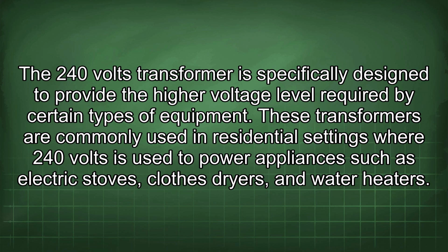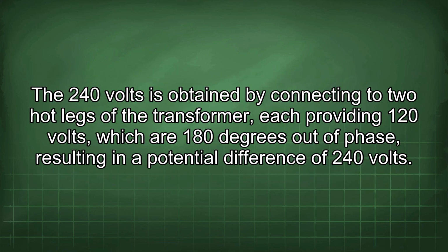These transformers are commonly used in residential settings where 240 volts is used to power appliances such as electric stoves, clothes dryers, and water heaters. The 240 volts is obtained by connecting to two hot legs of the transformer, each providing 120 volts, which are 180 degrees out of phase, resulting in a potential difference of 240 volts.